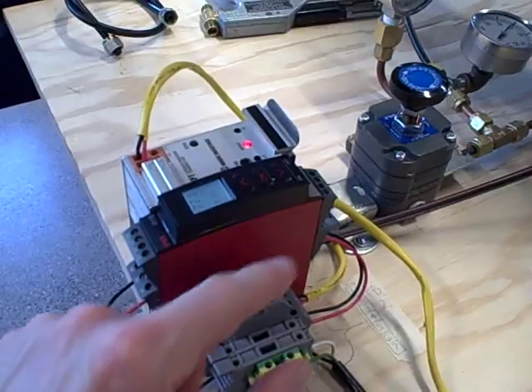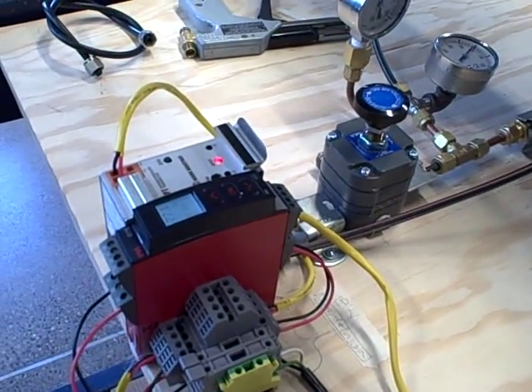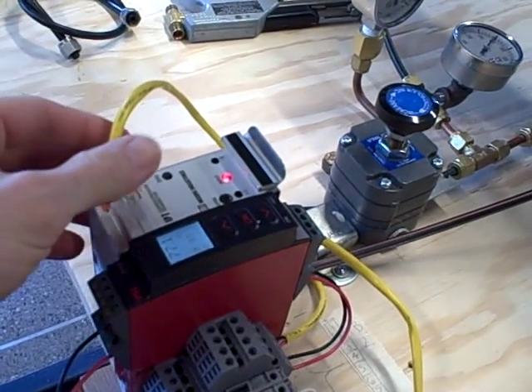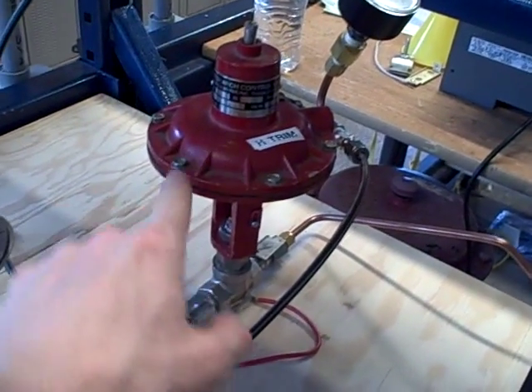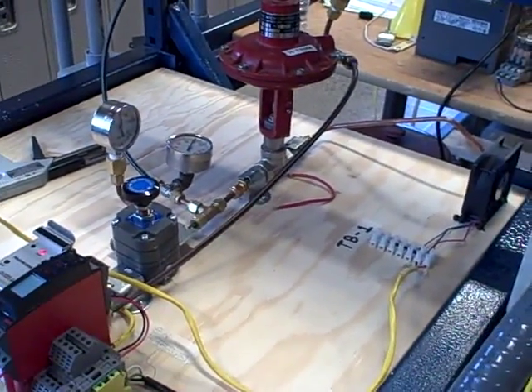That 4 to 20 milliamp signal goes through a set of cables onto our PLC control in this enclosure. The PLC then generates a 4 to 20 milliamp output signal, driving this I2P transducer, sending air pressure to the control valve, which directs how much compressed air to send to the turbine. So we have a working feedback loop for turbine speed control.